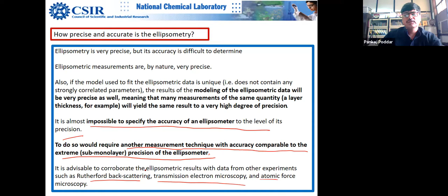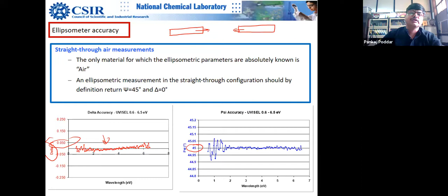And one of the best ways to measure this, it's not required, but if you are curious, is to keep the arms in the transmission geometry and then just measure without any sample. So delta should be almost close to zero, and you can see that this fluctuation here is very small. This value is 0.05 and minus 0.05. That tells you that this is highly accurate. So ellipsometry can self-check its own accuracy as well as precision. Similarly, you can see that the psi value should be 45, and it is almost at 45. So this is a way to do quality control and check things.